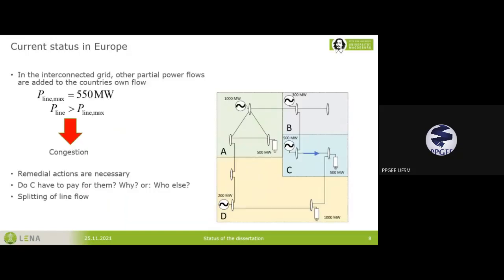But due to the fact that you have an interconnected system, on this line that connects this generator and this load, you will have not only the power flow that is produced based on the zone, you will also have additional power flows. So for example, the generator here in zone B will also feed into this load in zone C and into this load in zone D. So you will have a higher power flow in this line, and also the generator here in zone A will have a partial flow on this line in zone C that is connecting this generator and this load.